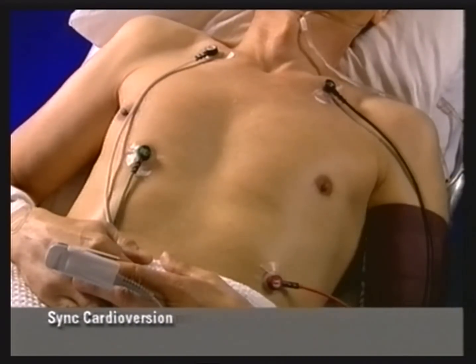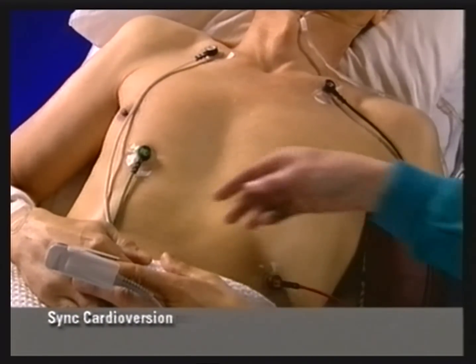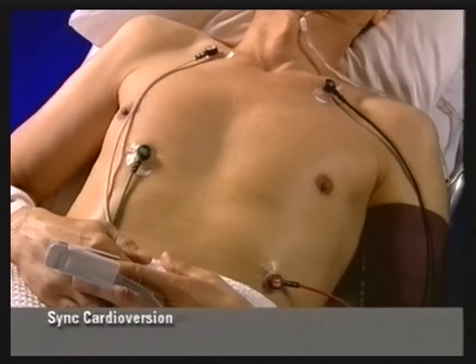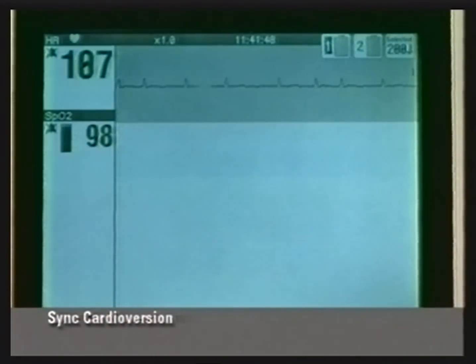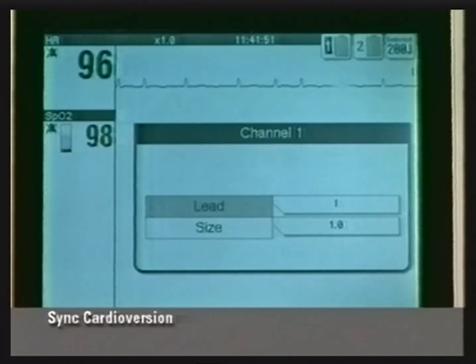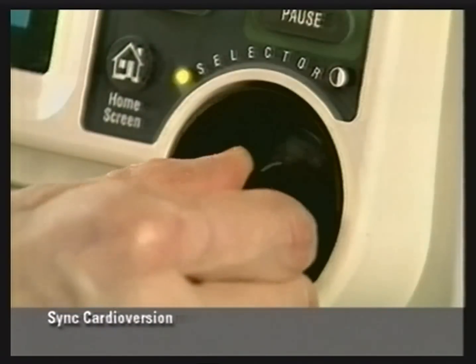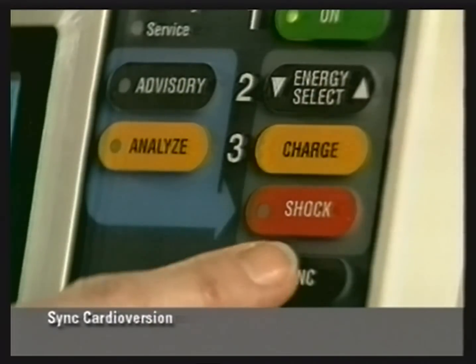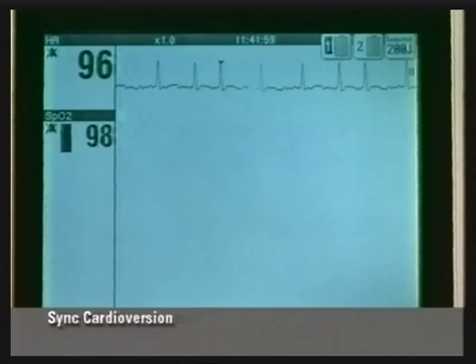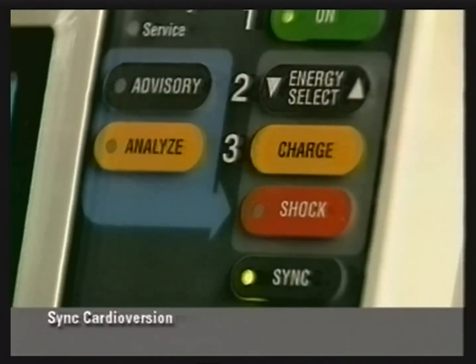To perform synchronized cardioversion, prepare the patient for the procedure according to your local protocol. Connect the patient to the ECG electrodes and cable as previously described in this video. Select the ECG lead with the greatest QRS amplitude or height. Press sync. Sense markers should appear on the R wave and the sync LED flashes with each detection.